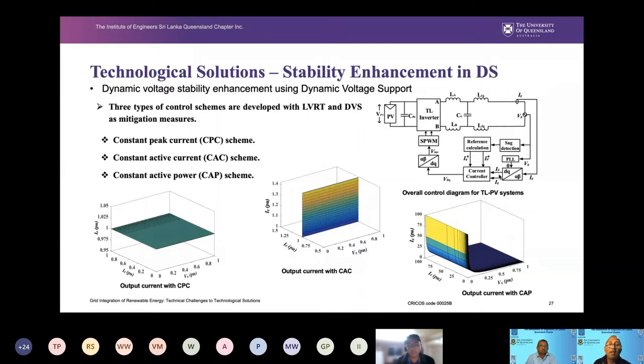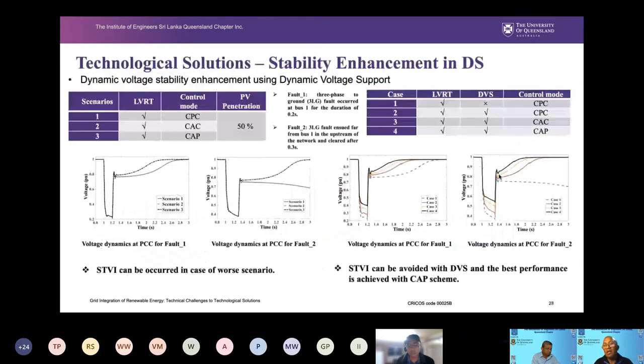One is a constant peak current scheme. The other is a constant active current scheme. The other is a constant active power scheme. I don't want to go into the technical detail of this. What we are trying to do is use the capability within the rooftop PV. Not every rooftop PV can be installed with this, but one or two in a proper location and of appropriate size can be. With this dynamic voltage capability, we can show that, not only for a closer fault but also for a far away fault, which is the more problematic one, we can overcome this dynamic voltage stability problem, which is a threat to the distribution system when we have a high penetration of renewable energy.